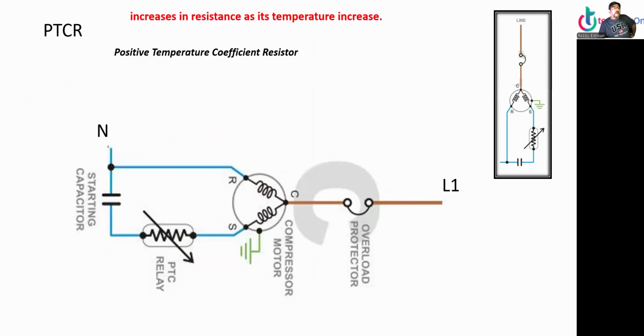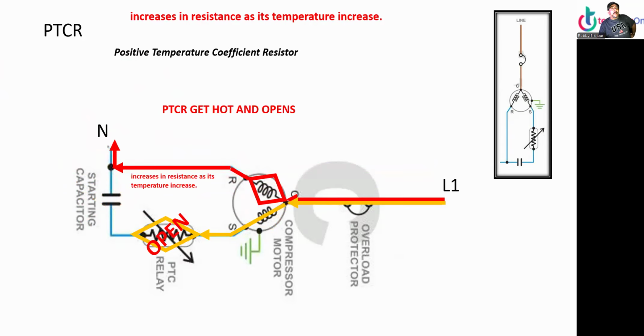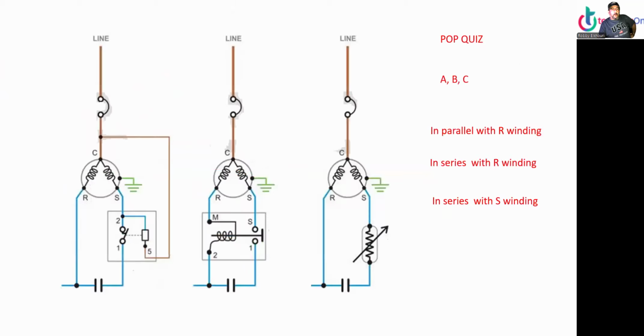Alrighty. Now, how they work is power comes in L1 and out to run. And also to start, because the PTC is closed, right? And start capacitor, and out. Now, the PTCR gets hot and opens. So when it opens, no more power in the start winding, only run. It's pretty simple.